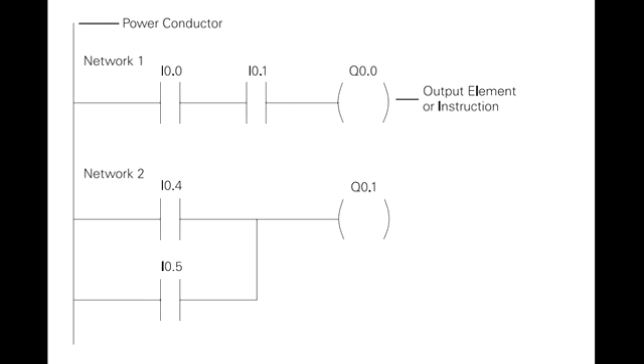The left vertical line of a ladder logic diagram represents the power or energized conductor. The output element or instruction represents the neutral or return path of the circuit. The right vertical line, which represents the return path on a hardwired control line diagram, is omitted. Ladder logic diagrams are read from left to right, top to bottom.